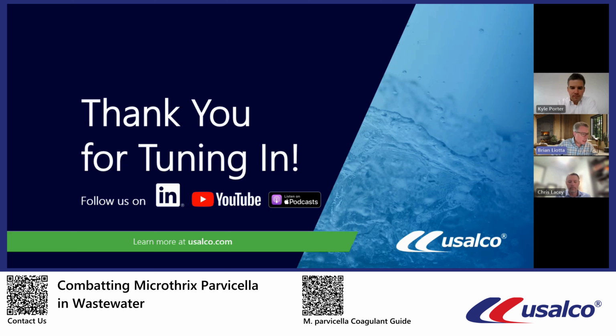First question, guys. Is there a way to jar test specifically for Microthrix? Just like Kyle mentioned, not specifically for Microthrix, but you can jar test for phosphorus removal. And once you determine the correct product for phosphorus removal, that will correlate to Microthrix very well from what we found. That was a good question.